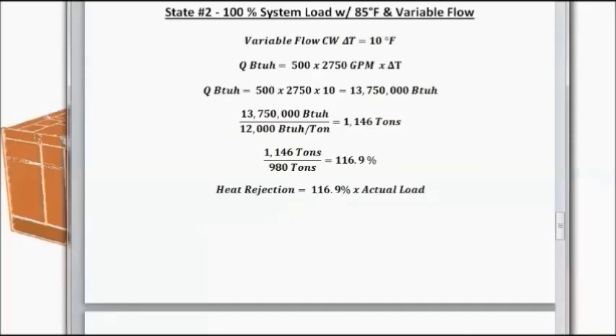In state 2, we changed the control method to variable condenser water flow. The flow rate just dropped slightly. And we can confirm this by checking. When we check the actual load, it could be about 980 tons, just below maximum capacity. And again, we calculate the heat rejection and see that it has decreased insignificantly with this small change. So we're at 116.9% of actual load for the heat rejection component.